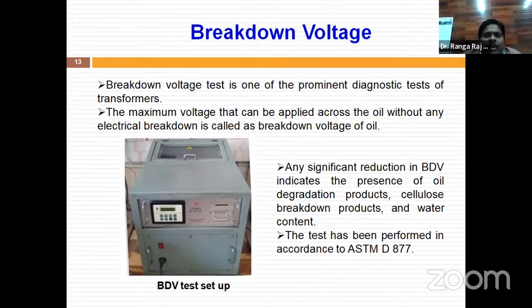So the oil should be electrically strong, that's why the dielectric strength should be high. For a good insulating material, a fresh insulating oil inside the transformer, the dielectric strength is 60 kilovolts.